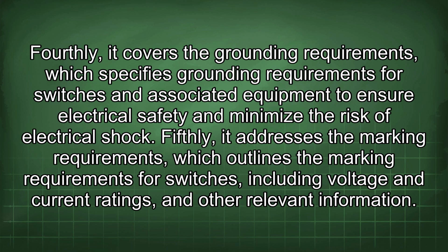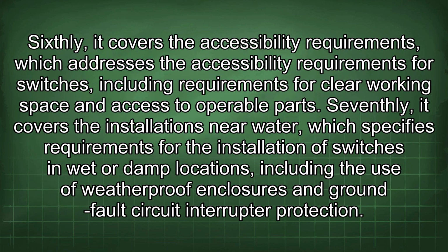Fourthly, it covers the grounding requirements, which specifies grounding requirements for switches and associated equipment to ensure electrical safety and minimize the risk of electrical shock. Fifthly, it addresses the marking requirements, which outlines the marking requirements for switches, including voltage and current ratings and other relevant information. Sixthly, it covers the accessibility requirements, which addresses the accessibility requirements for switches, including requirements for clear working space and access to operable parts. Seventhly, it covers the installations near water, which specifies requirements for the installation of switches in wet or damp locations, including the use of weatherproof enclosures and ground fault circuit interrupter protection.